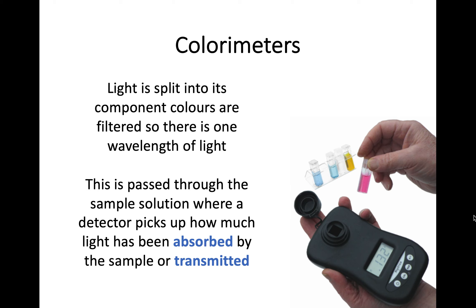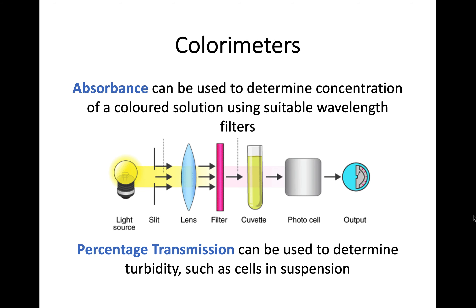When passing light through the sample you can use different filters. The colorimeter picks up how much light has been absorbed and also how much light has been transmitted by that sample. The absorbance of the solution can be used to determine its concentration, depending on what filter you use. The percentage transmission can be used to determine turbidity — that cloudiness we talked about. The higher the transmission, the less cloudy and less turbid your solution is. This is useful when analyzing things like cells inside a solution.